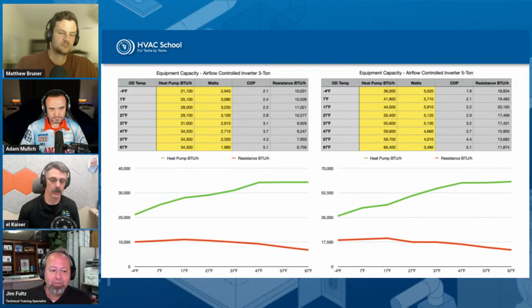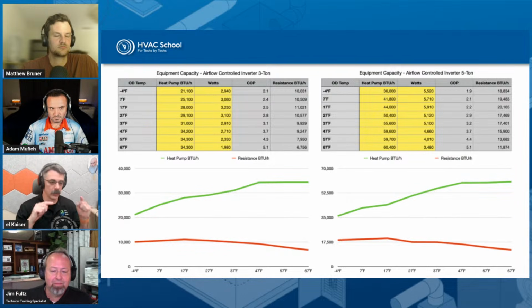Yeah, and for that, you really got to look, like you said, at bin data. How many hours a year are you going to run at these temperatures? For me, where I'm at, and even you, Adam, probably where you're at, you're going to see a lot of the year above that 17 degrees. There's a significant amount of the heating season. We might get several weeks where it's below 17, but there's months and months where it's above 17 degrees most of the time, or hours really, because the temperature changes throughout the day. And in a couple more slides we'll get into a little bit more of that balance point, the thermal balance point between the house and the heat pump.